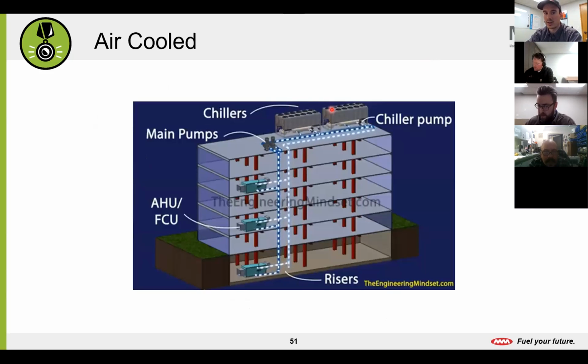This graphic's pretty good because it shows we have our chillers outside where they can reject heat into the air. Our water is flowing through these chiller barrels. I'll show you right here, this white line is going to be warmer water that goes into the chiller barrel, rejects its heat, so it comes out colder. That heat that it rejected gets rejected outside, and then we're delivering chilled water with the use of these water pumps down to some central air handlers on each floor that have a chilled water coil where a fan blows air over the chilled water, and then that supply air will go into the ductwork and feed maybe some VAVs or different equipment in that space. So this would be that central plant we talked about where our cooling is done at a remote location. And then we're supplying all that cooling medium, the water, inside.